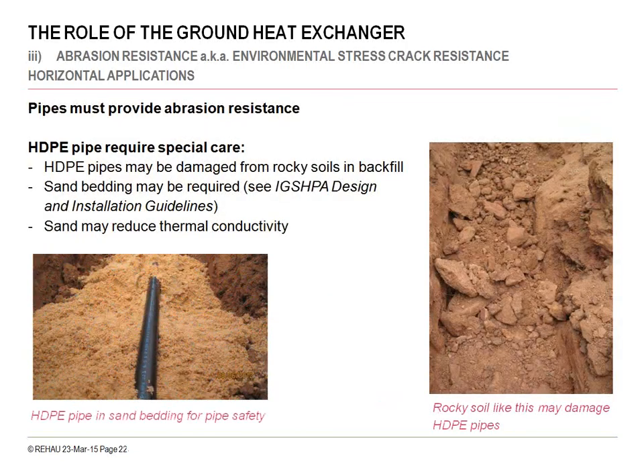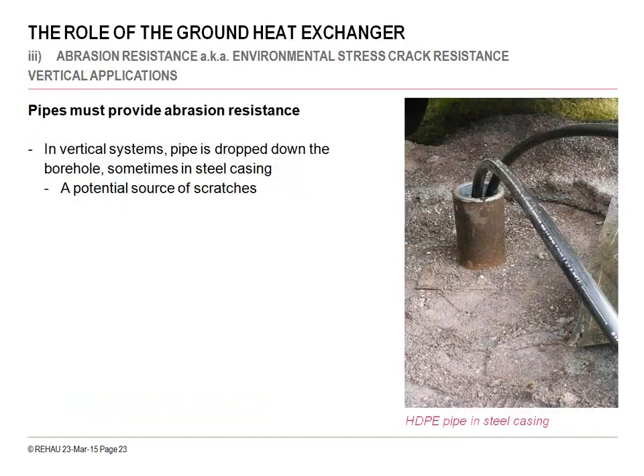Now, on the abrasion resistance and puncture resistance with high-density polyethylene pipes, the HDPE guidelines want horizontal piping of HDPE to be in a sand bed. They do not want to have the rocky type of soil that you see in the image on the right, as it may create some damage and puncturing the pipe. Also, you want to be safeguarding against abrasion, or have materials with good abrasion resistance and safeguarding against nicking up the pipe. In this case, you see an image of high-density polyethylene being inserted down a vertical borehole where you have steel casing.